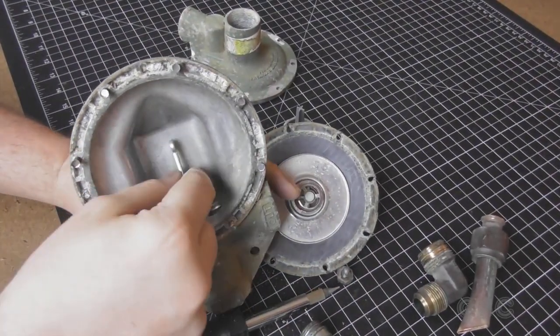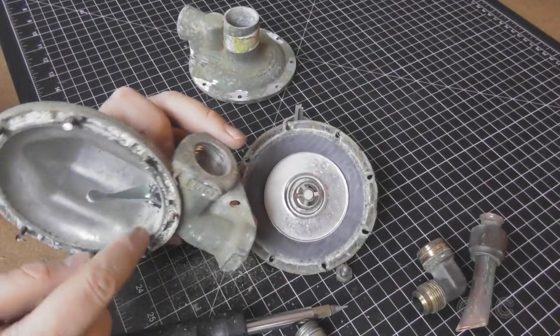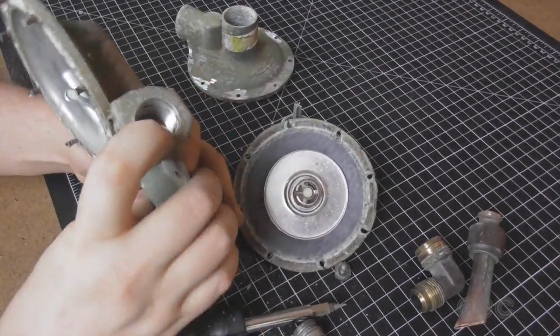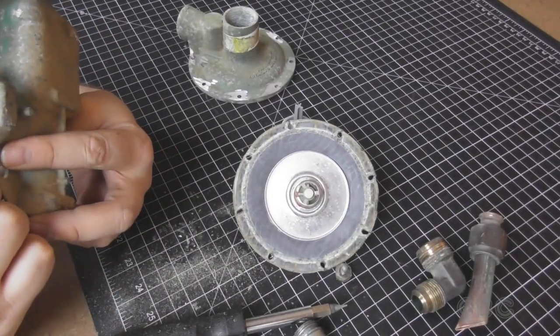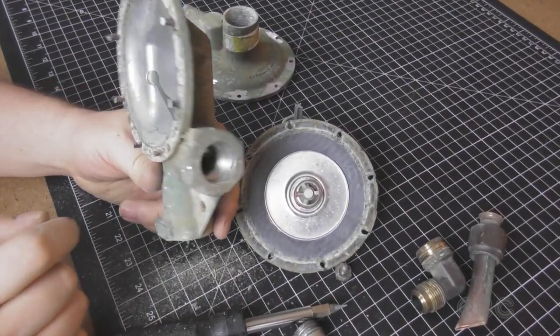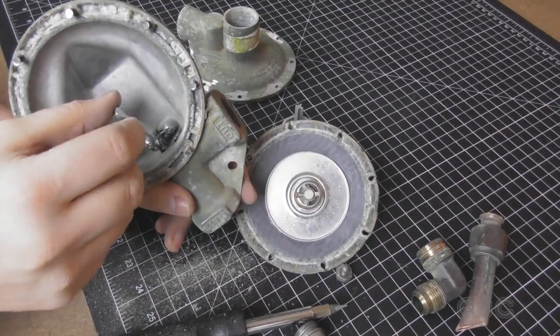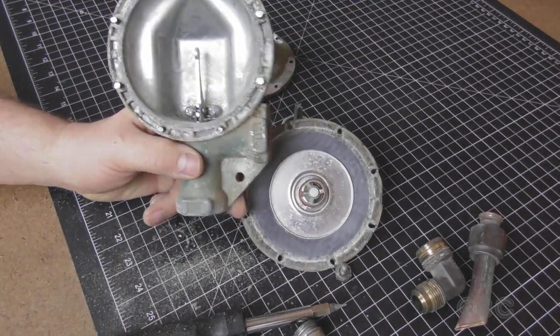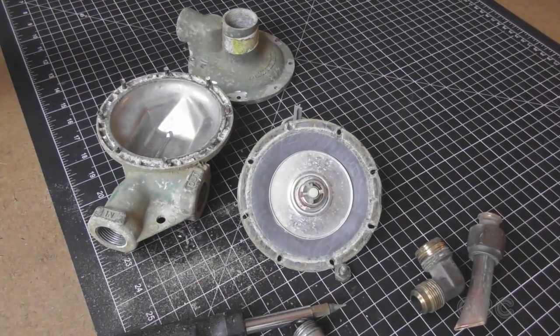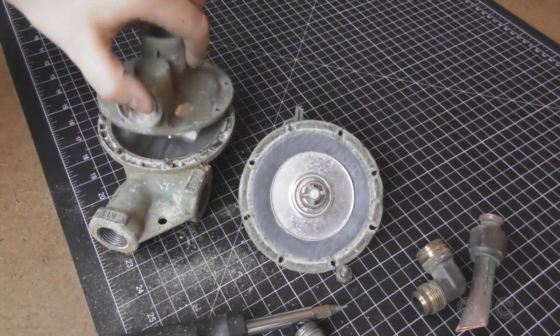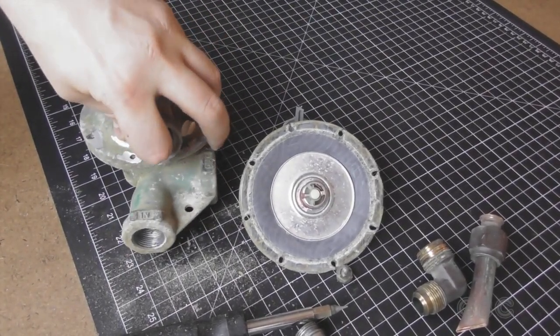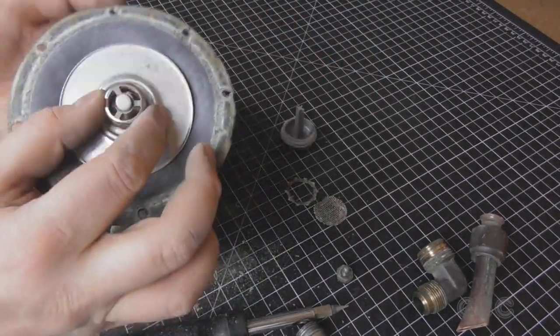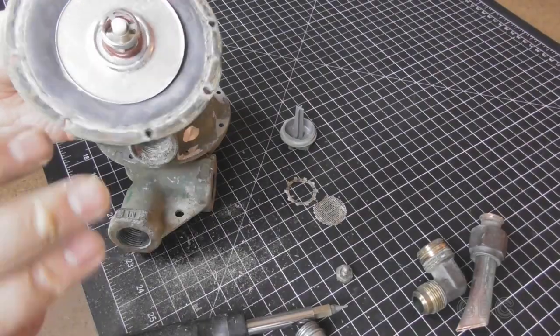So the gas comes in the inlet, fills the area behind the diaphragm, pushing against the spring, closing the valve, and stopping flow. When the pressure goes down, the spring will push the diaphragm back and allow more fuel to come in. The vent is to allow the front side of the diaphragm to be at atmospheric pressure. As it moves it has to allow air in and out.